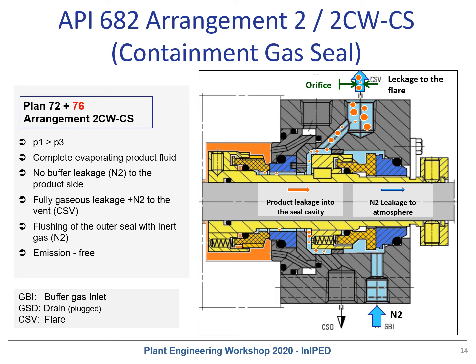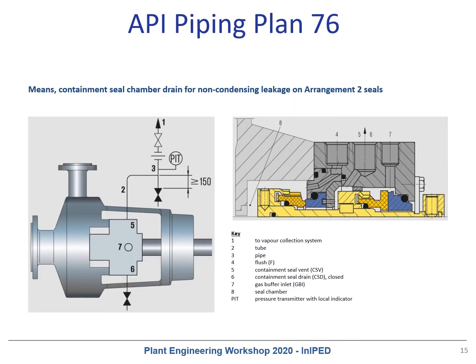The same seal configuration can also be combined with piping plan 72 plus 76. Piping plan 76 is used for hydrocarbons which fully vaporize in the containment seal cavity and are then vented to the flare system. Piping plan 76 is defined as a containment seal chamber drain for non-condensing leakage on an arrangement 2 seal, meaning the leakage is sent to flare to minimize process emissions to the atmospheric side.